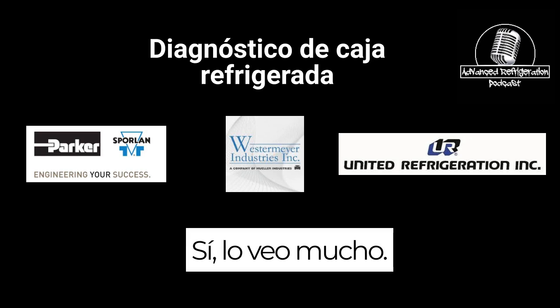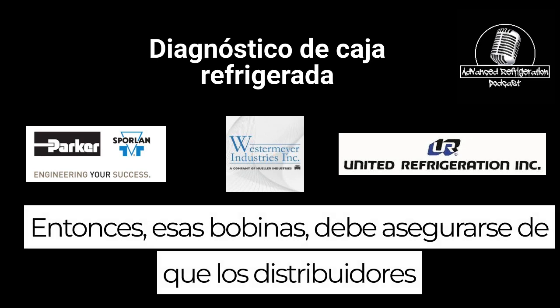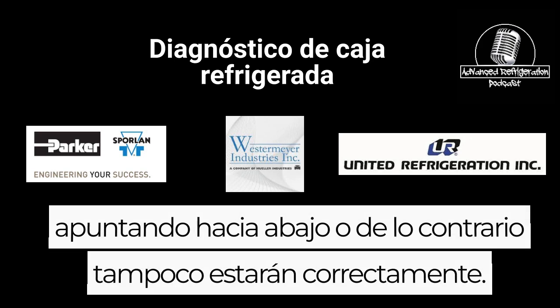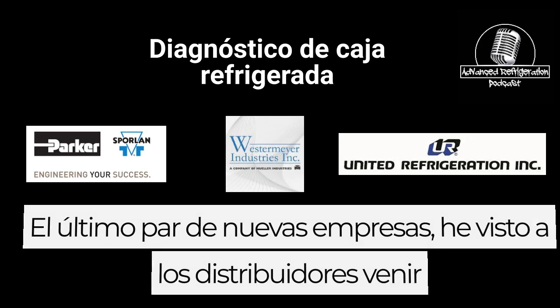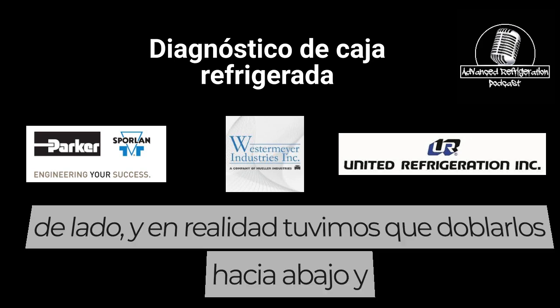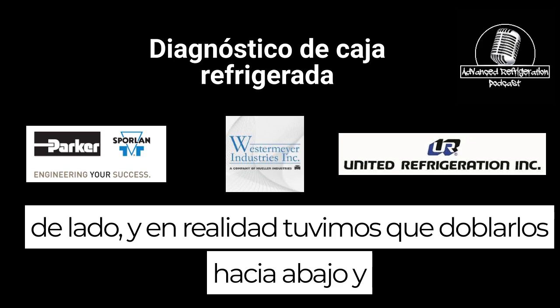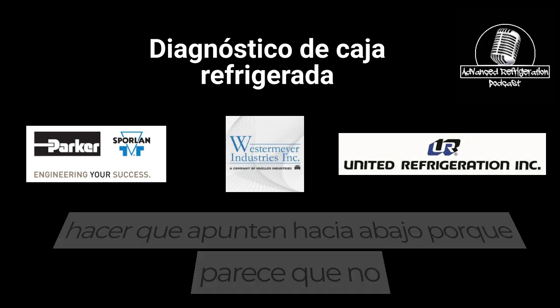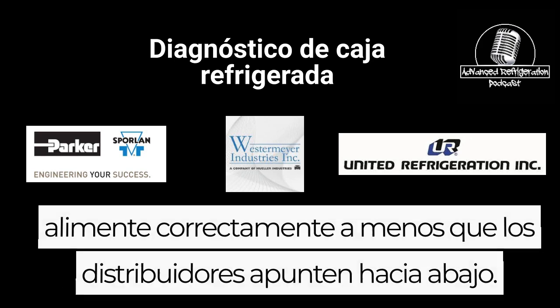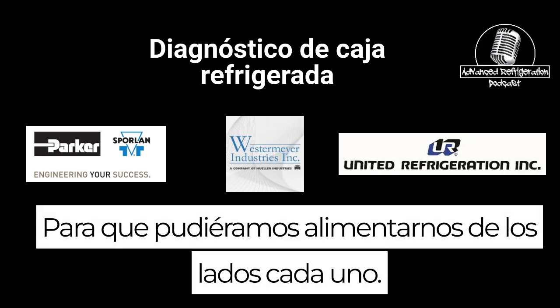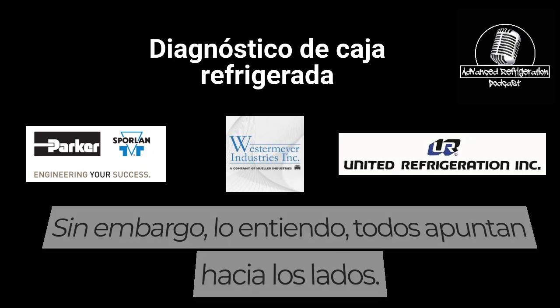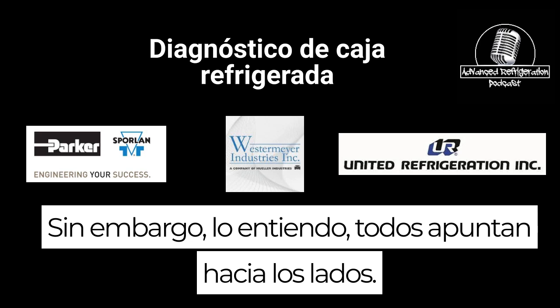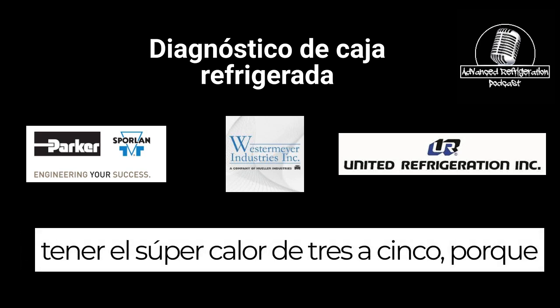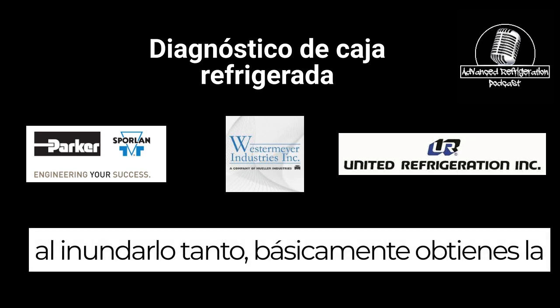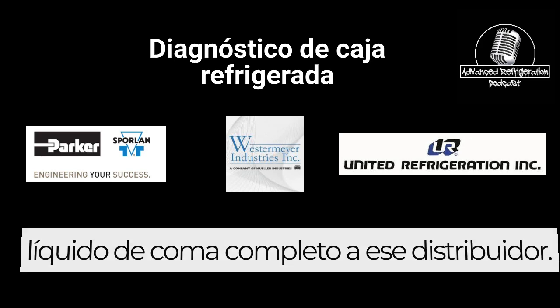Yeah, I used to see that a lot. I mean, a lot. Another thing on those coils: you need to make sure the distributor's pointing down, or else they won't feed properly either. On the last couple startups I've seen distributors coming out sideways, and we actually had to bend them down and use a street 90 to get them to point down, because they don't feed properly unless the distributor's pointed down so it can feed off the sides. Every single one I get of those, they're all pointing sideways. I think that's why Heatcraft wants you to have the superheat at 3 to 5, because by flooding it that much, you're getting the full column of liquid to that distributor.